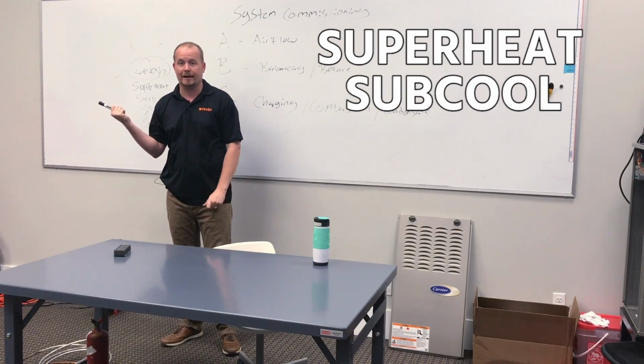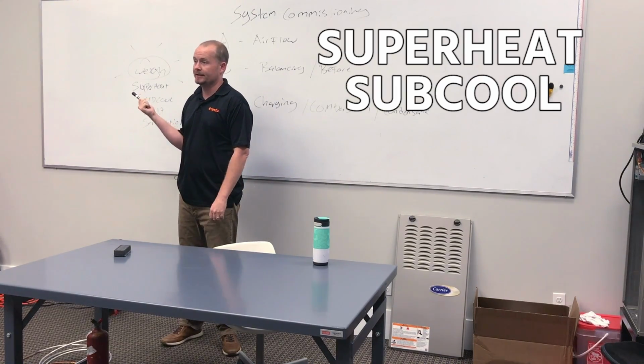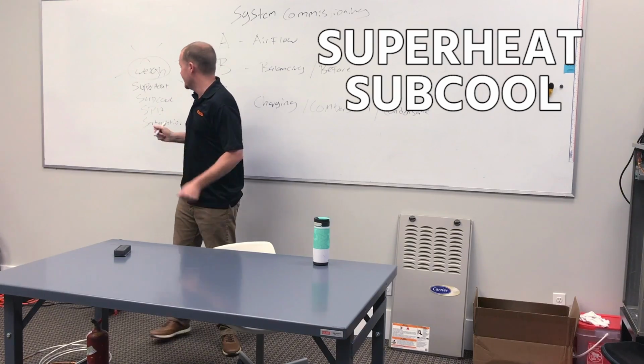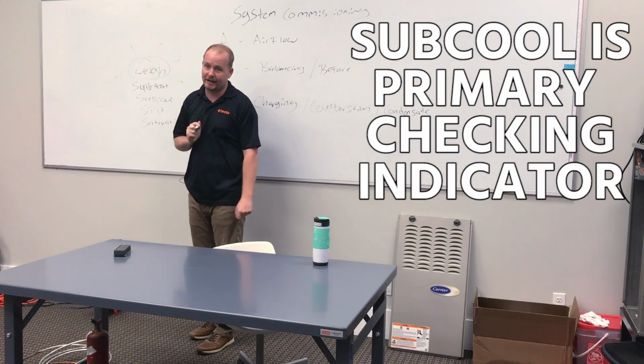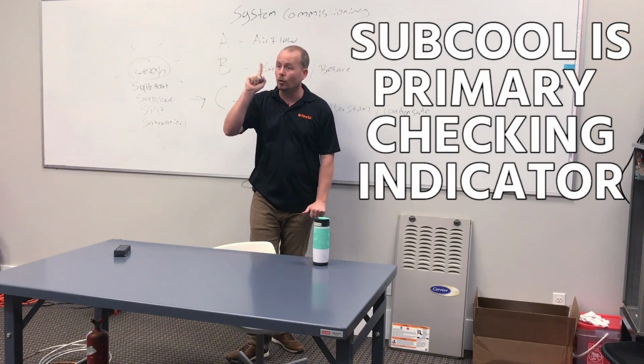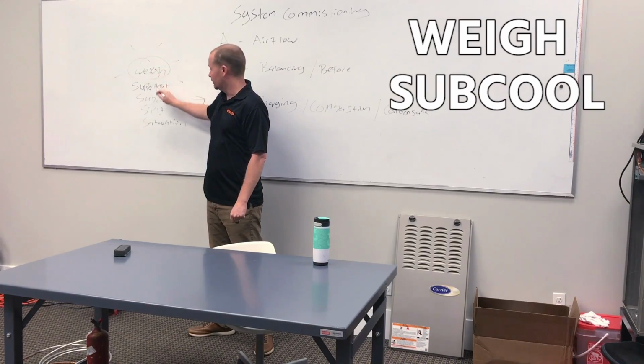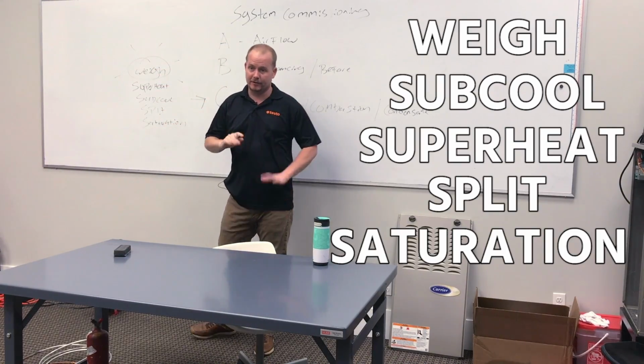Most of the systems we work on nowadays, if not darn all of them, on installs are TXVs, which means subcool is our primary checking indicator. But it is not our only indicator. Weigh, subcool, superheat, split, saturation. Those are the things we're looking at.